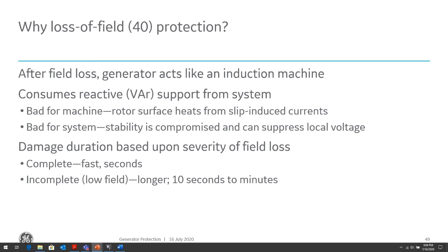It's bad for a system and it's bad for a machine. It's bad for a machine because the rotor now gets overheated because of the slip-induced currents, because the high currents in the stator get induced in the rotor. The stability of the system is also compromised, because since the machine is sucking VARs, it's going to start to suppress the voltage. Then other machines are going to start to respond by supplying VARs, and they could get into an overexcited condition. So this could be a whole spiral of instability where everything starts to spiral out of control, and we could have all the machines tripping and a widespread blackout. So we want to be able to detect this condition, and the protection element we use is called a loss of field protection.